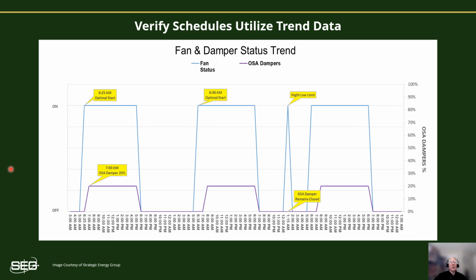Note this low limit spike around midnight running until about 2. The dampers here are kept shut, and again, this is what we want them to do. The system will be able to provide all of its heat into getting the building back above the night low limit temperature again. So from the information we see here, this system appears to be operating correctly.